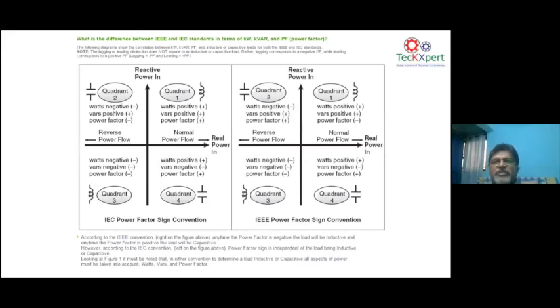On one side, if you are exporting power to the grid, yes, you should export both reactive power and active power to the grid. You cannot export active power and draw reactive power from the grid. That means TNEB can penalize the consumer. So you have to make sure that the controller works in 4-quadrant operation efficiently so that this flow of active power and reactive power is managed carefully.